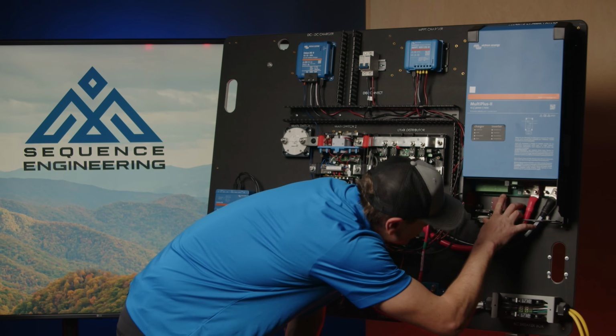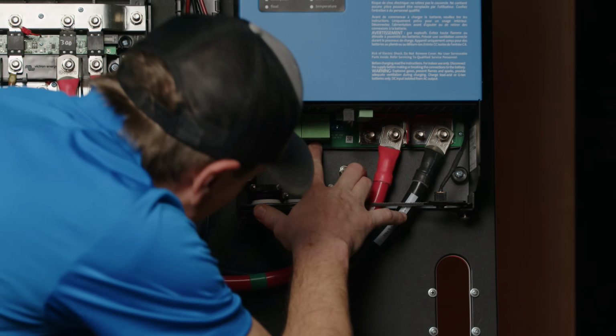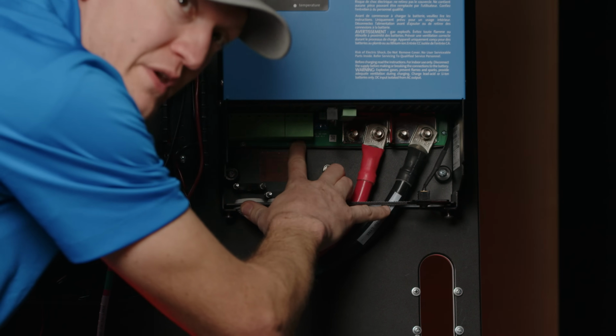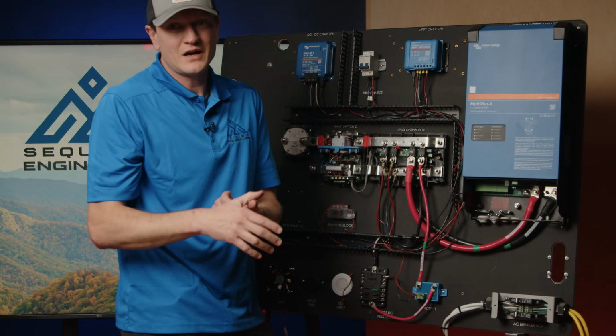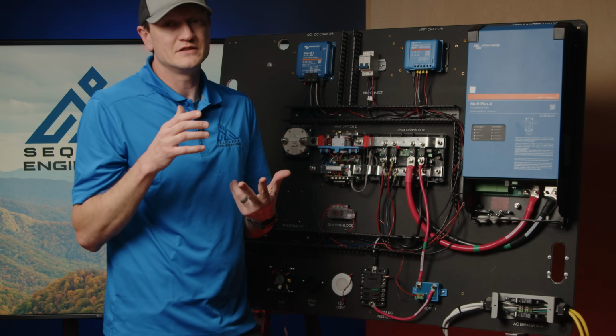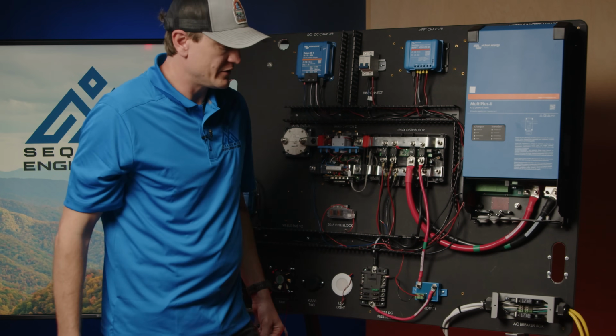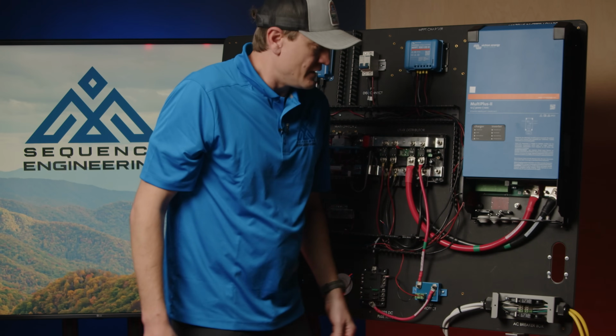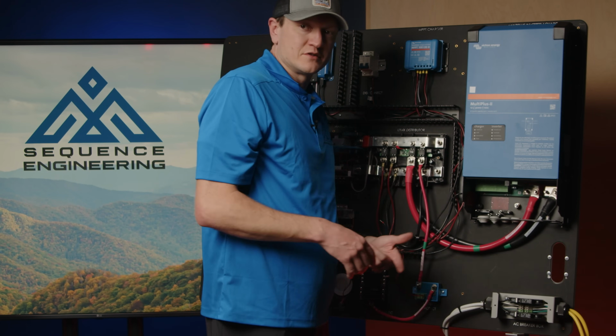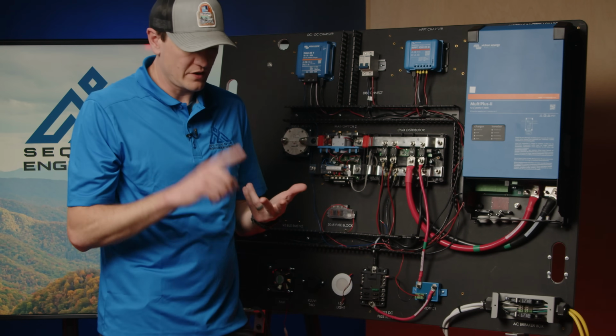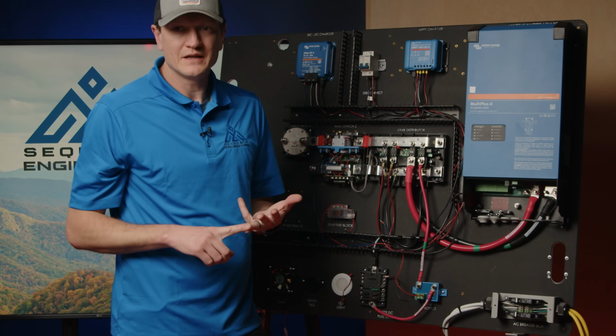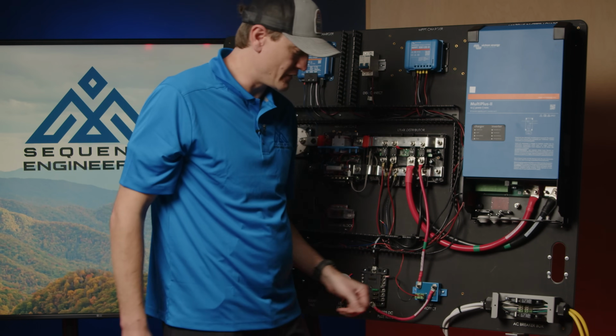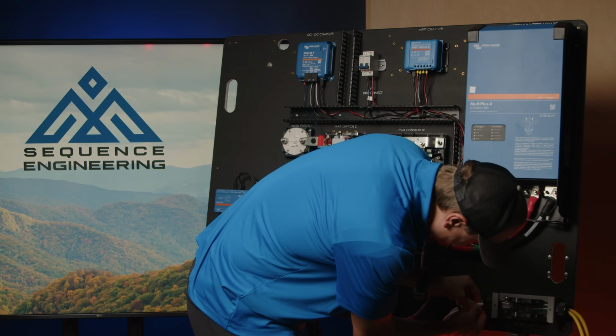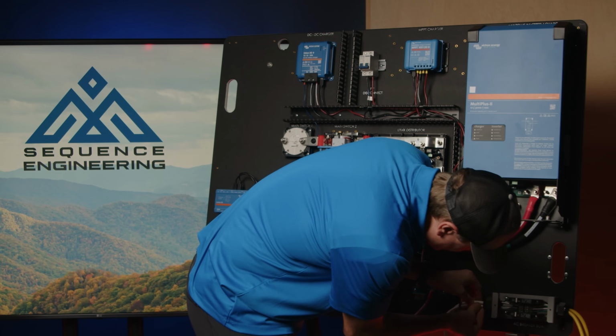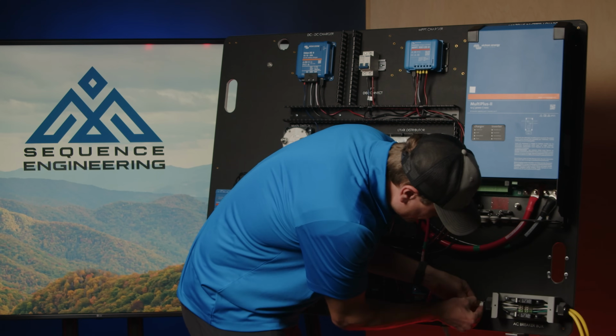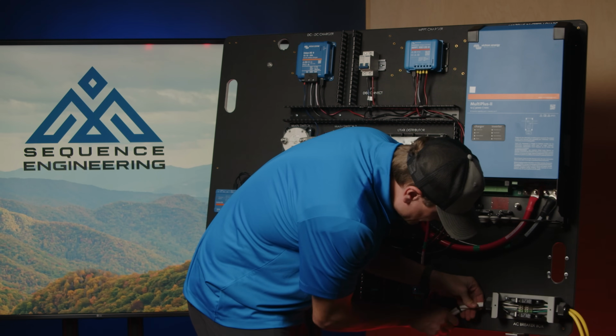On each location you have an L, an N, and a PE. L is your hot wire, PE is your ground, and N is your neutral. L stands for line in this instance, and we will wire them that way. So L will be our black wire, PE our ground will be our green wire, and N will be our neutral or white wire. I'm going to go ahead and wire up each one of these and show you some things you need to be aware of.